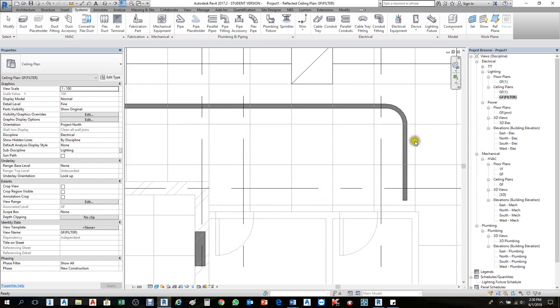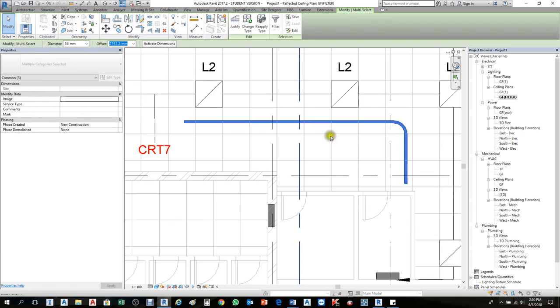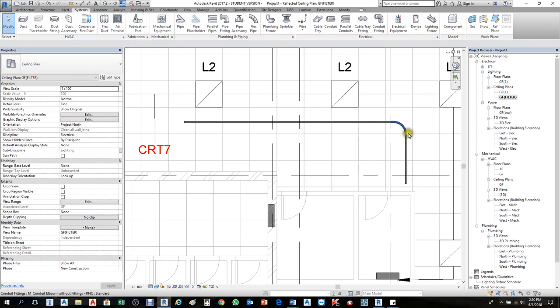If we don't have a 25mm conduit available, we need to add it. To select all connected conduits, hover your mouse over the conduit and press Tab once — it will select every joined conduit. This conduit is 53mm diameter; I will change it to 25mm and press OK.